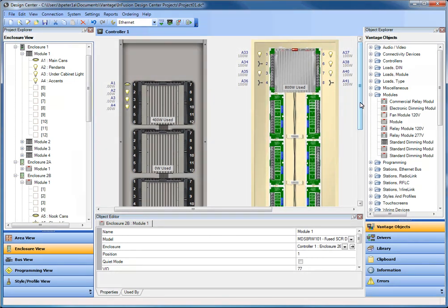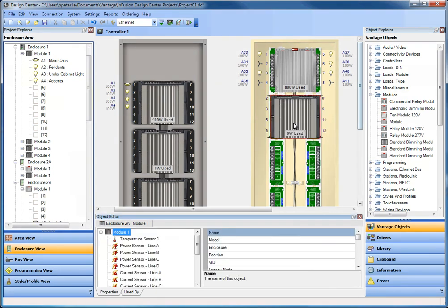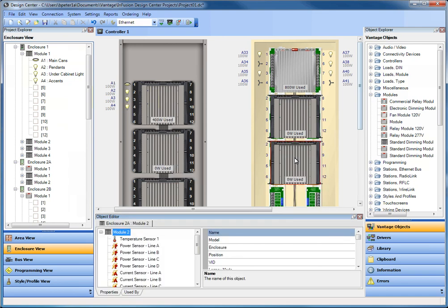So finishing out that process will allow you to have a new enclosure, a new set of modules, and then you can go through and delete these modules once you've dragged over all those loads. Now, it also may happen that you have a need for an older enclosure to not be changed out. It's already installed and all you're trying to do is either add a module to the project or to change out an old module for a new module and the older dimming modules aren't available anymore. So what we're going to do here is drag a standard dimming module onto the enclosure, or I could have right clicked and said add module, and because it's the default module, it will add it directly to that position.